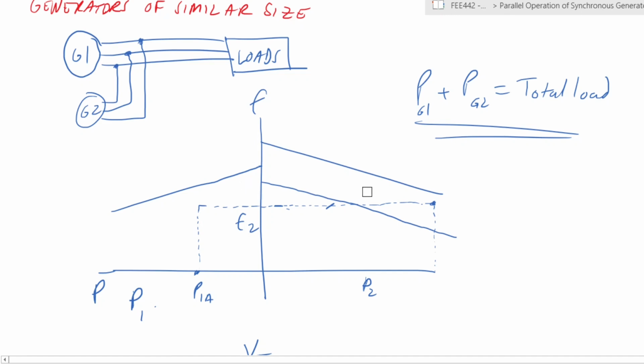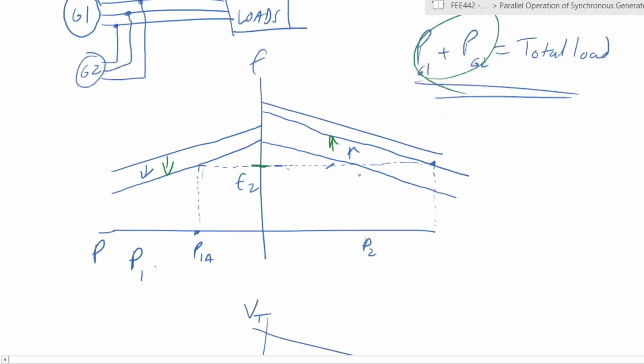Delete this one. Right? So you had your initial set points there, but now you need to have a new set of set points here. Okay, so in this case, you are decreasing your set points, but in the other case, you are then having to increase, right? So in order to maintain the same ratio of P1 to P2, supplying the same load, remember, the sum total must remain the same. So that value has to remain the same. In order to keep the same frequency, you'd have to decrease the set point of generator 1, but increase the set point of generator 2. So that's the case number 2 that we've written here.